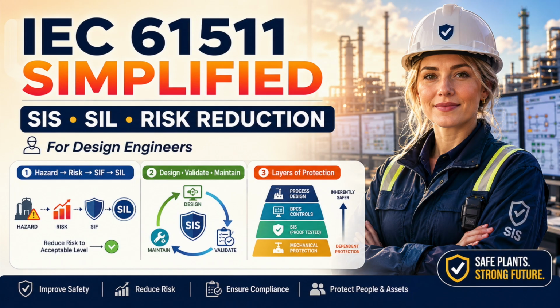A bypass must also be treated as a temporary change to the safety case. When you bypass a safety instrumented function, you remove or weaken a protection layer. Who authorized it? How long can it remain? What compensating measures apply? Who knows it is active? How is it communicated at shift change? How is restoration verified? A bypass that remains because everyone assumes someone else owns it is not a maintenance issue. It is a management failure.